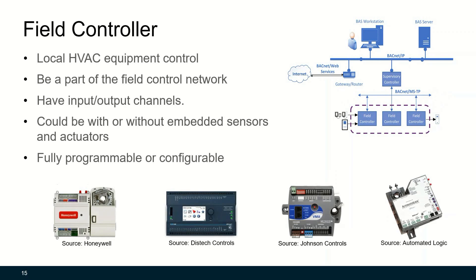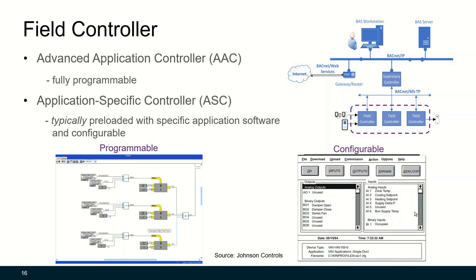Field controllers are typically used to control local HVAC equipment and are part of the field control network. They have input and output channels, and could be with or without embedded sensors and actuators. They are either fully programmable or configurable. In a programmable controller, you can program any sequence you want. In a configurable controller, there is pre-configured and pre-loaded software — you can only select available points and configure certain inputs, outputs, and parameters, but cannot freely program any sequence.